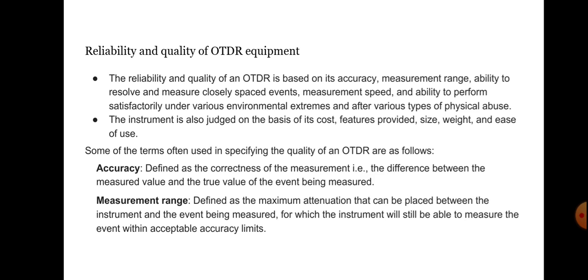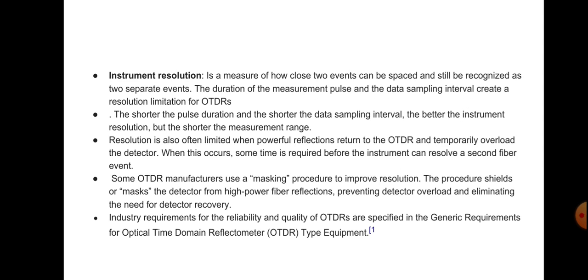The instrument is also judged on the basis of cost, features provided, size, weight, and ease of use. Accuracy is defined as the correctness of the measurement — the difference between the measured value and the true value of the event being measured. Measurement range is defined as the maximum attenuation that can be placed between the instrument and the event being measured for which the instrument will still be able to measure the event within acceptable accuracy limits. Instrument resolution is a measure of how close two events can be spaced and still be recognized as two separate events.